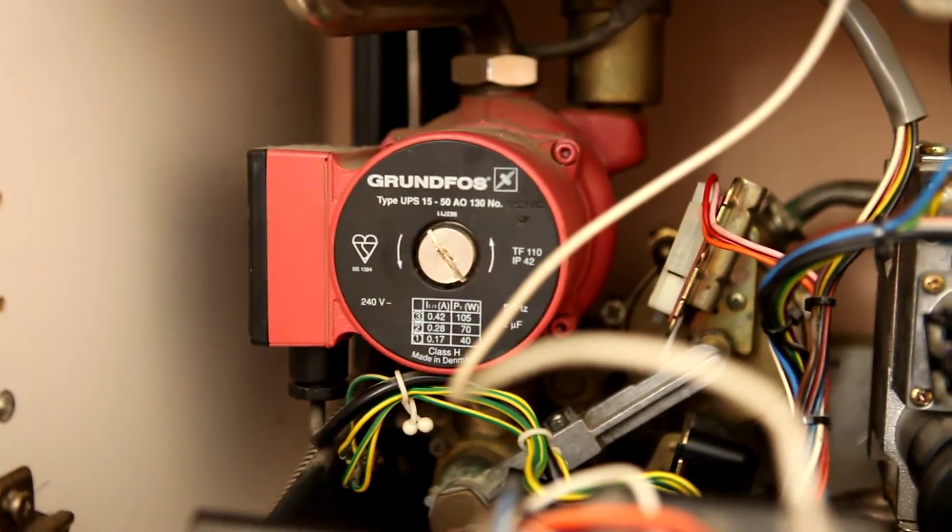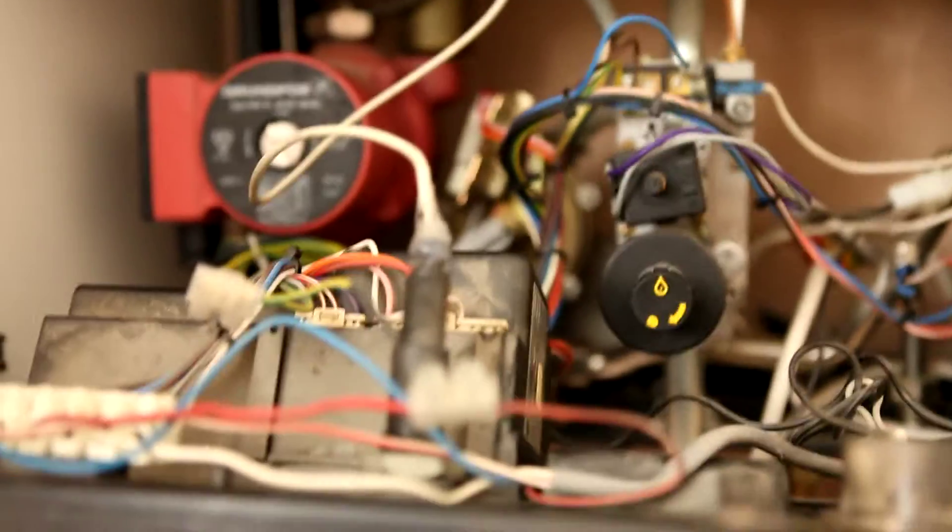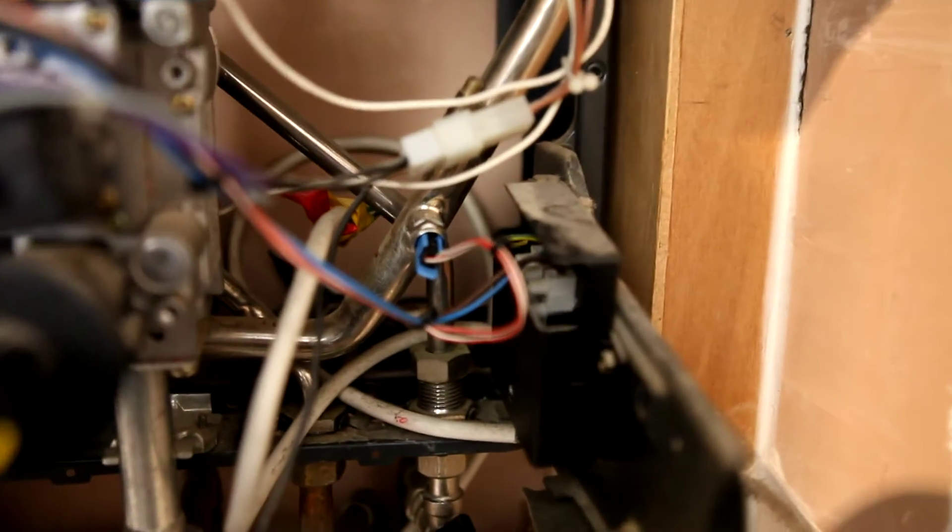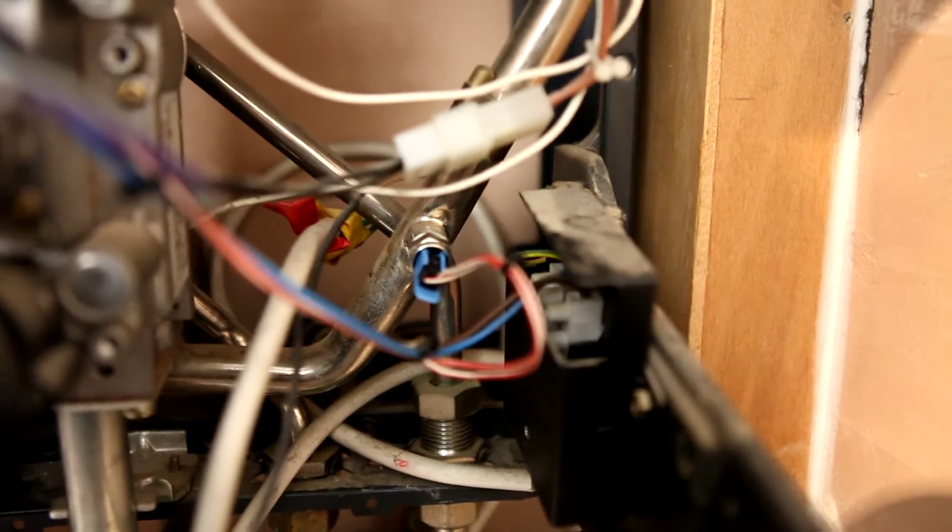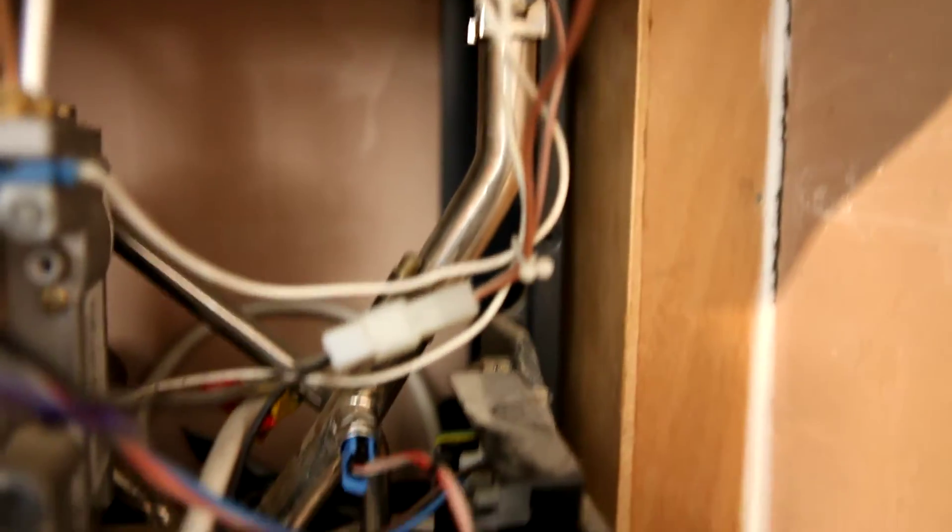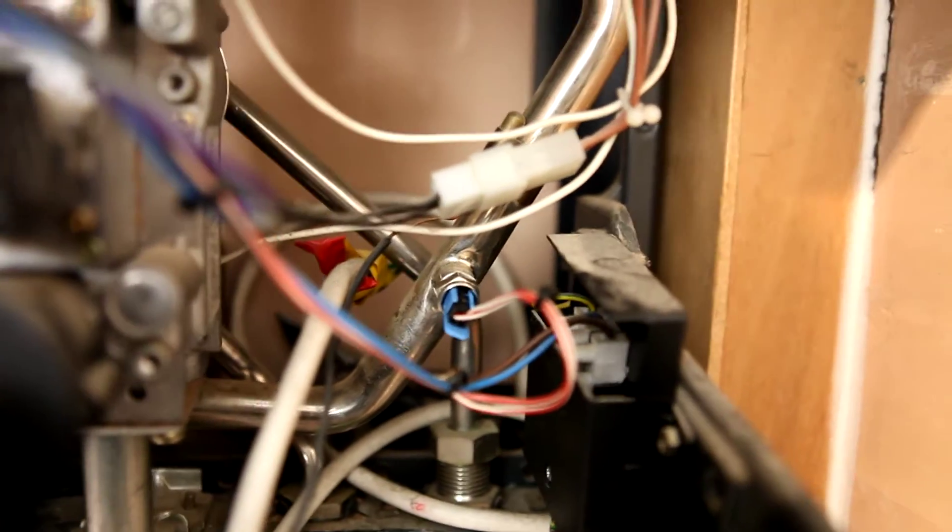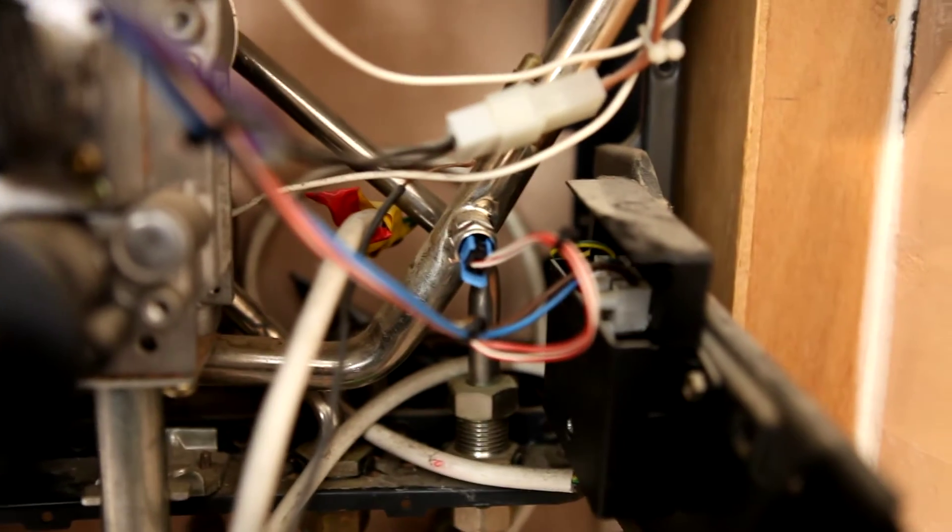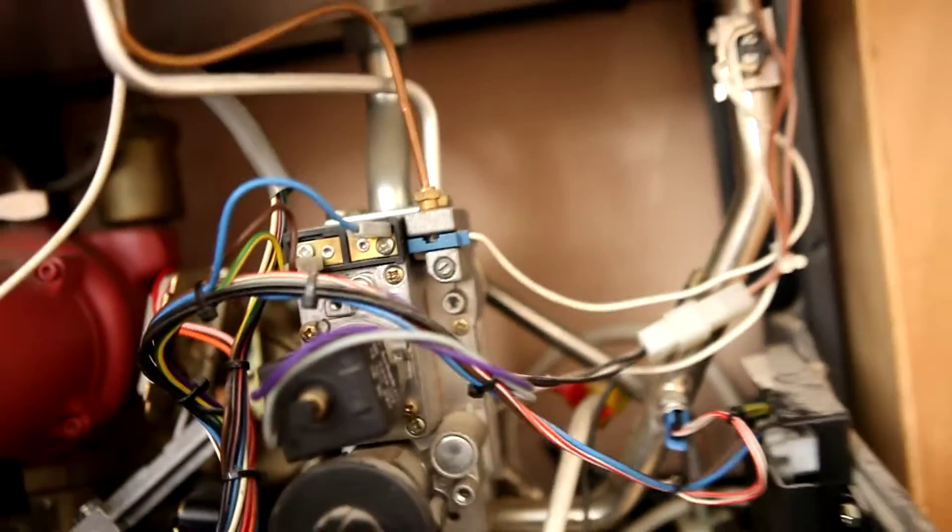But the other thing is, could that be part of the problem? Well, we've had several engineers in, and they've tried all sorts of things, changing the domestic hot water circuit thermistor, which is that blue thing there connected to the primary hot water circuit.